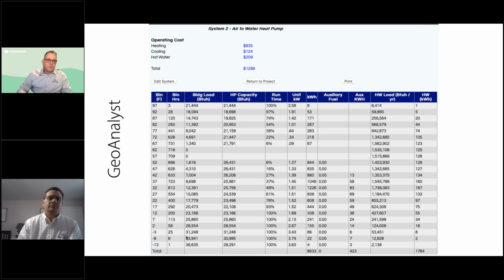The way you read these bin reports, you have on the far left your bin temperatures. Those are 5-degree bins. The next column is bin hours. So those are the average hours per year at each of those bin temperatures. Then there's the building load and the heat pump capacity. So it will show percentage runtime if that unit is not modulating, in other words. So when you see a percentage, that means it's cycling on and off. When you start to see 100% runtime, that means it's trying to match the load. Being a variable speed compressor, it's going to ramp up, ramp down, try to match the load, and also bring on the vapor injection when needed.